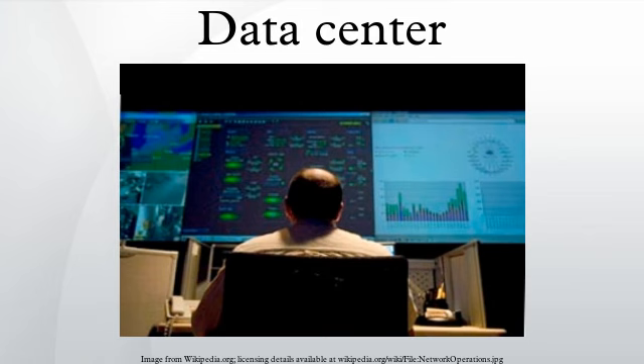High-sensitivity smoke detectors, such as aspirating smoke detectors, activating clean agent fire suppression gaseous systems activate earlier than fire sprinklers. Sprinklers equals structure protection and building life safety. Clean agents equals business continuity and asset protection. No water equals no collateral damage or cleanup. Passive fire protection elements include the installation of firewalls around the data center, so a fire can be restricted to a portion of the facility for a limited time in the event of the failure of the active fire protection systems. Firewall penetrations into the server room, such as cable penetrations, coolant line penetrations and air ducts, must be provided with fire-rated penetration assemblies, such as fire stopping.